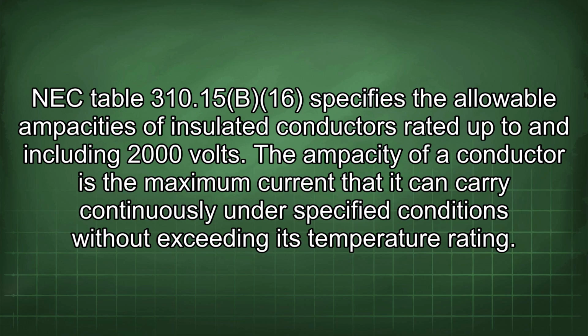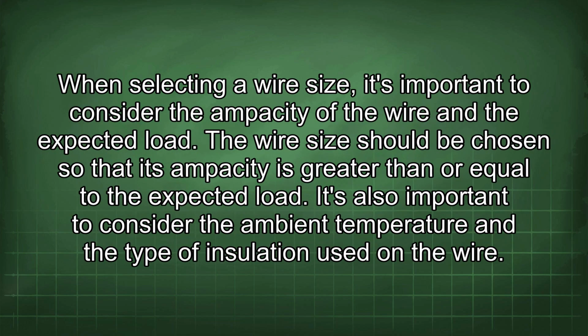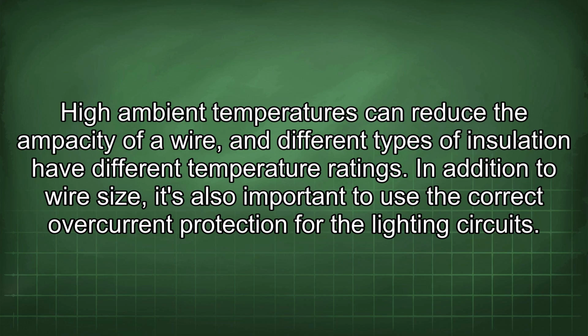The ampacity of a conductor is the maximum current that it can carry continuously under specified conditions without exceeding its temperature rating. When selecting a wire size, it's important to consider the ampacity of the wire and the expected load. The wire size should be chosen so that its ampacity is greater than or equal to the expected load. It's also important to consider the ambient temperature and the type of insulation used in the wire. High ambient temperatures can reduce the ampacity of a wire, and different types of insulation have different temperature ratings.